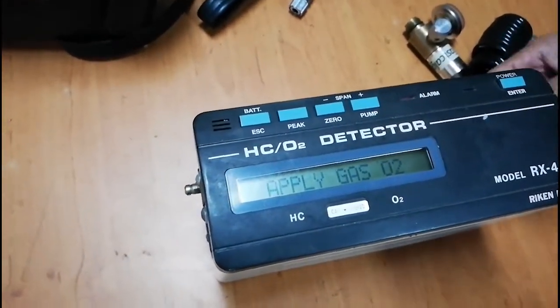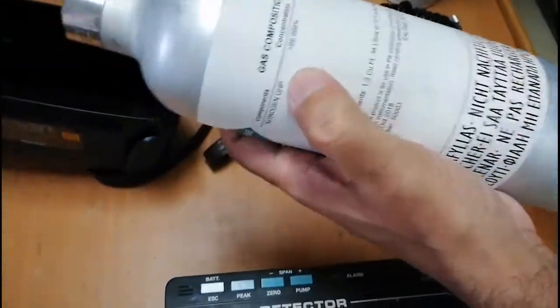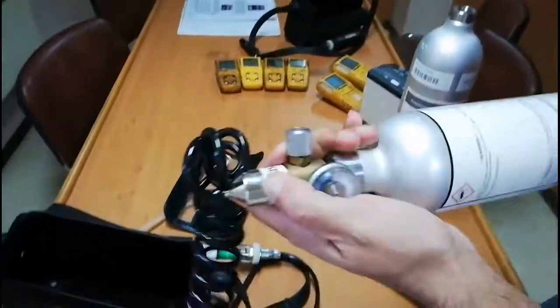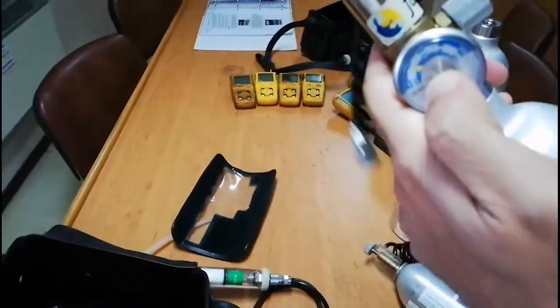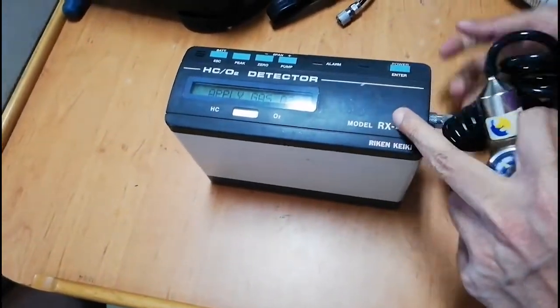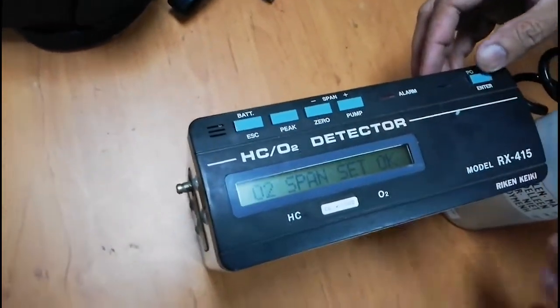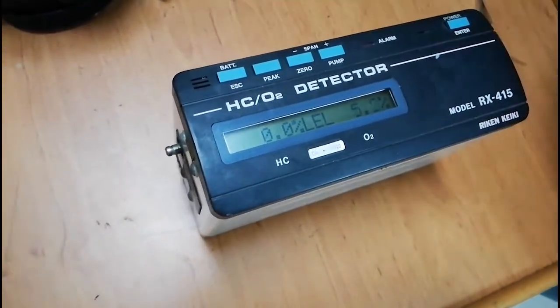Next it will ask to apply oxygen. For oxygen calibration we are using 100% nitrogen — so zero oxygen. I will connect the 100% nitrogen span gas to the inlet of the Riken Keiki RX-415. Press Enter and you can see it gradually brings to zero. Once it is steady at zero, it means no adjustment is needed for the oxygen sensor. I press Enter and auto span set is okay. I remove the hose and you can see LEL zero and oxygen 20.9%, which is the atmospheric oxygen content.